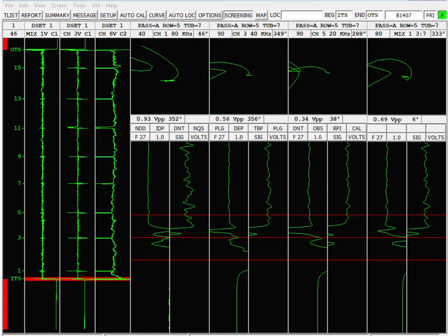When you're doing inspections of large components like chillers and steam generators, the best data quality occurs when you use mechanical probe drivers. The benefit of using mechanical probe driver systems is that the recorded data, which is always on the pull when you're using the bobbin coil probe, the pull speed will be consistent.